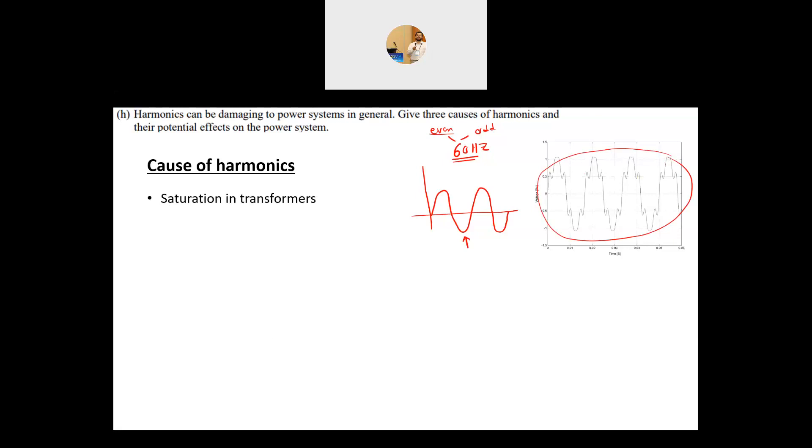The first cause is saturation in the transformer. The transformer itself, because of the saturation of the core, acts like a non-linear resistance in parallel with a non-linear inductor, so it produces some harmonics. When you have saturation, you produce more and more harmonics.